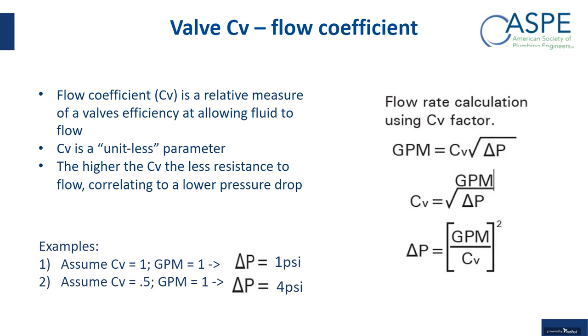Now let's say you took that same valve and the CV for whatever reason is 0.5. So the GPM is 1, the CV is 0.5, 1 divided by 0.5 is 2, and 2 squared is 4. So you can see how the square function impacts the pressure drop. As the CV went in half, the pressure drop increased by a factor of 4. That's something you need to pay attention to when you're selecting your valves.